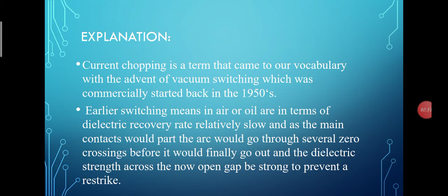The rapid deionization of contact space and blast effect may cause current interruption before it is naturally zero. Such an interruption of current before its natural zero is termed current chopping. This phenomenon is pronounced in the case of air blast circuit breakers, which exert the same deionization for all currents within their short circuit capacity, even though the instantaneous value of current being interrupted may be less than the normal current rating of the breaker.